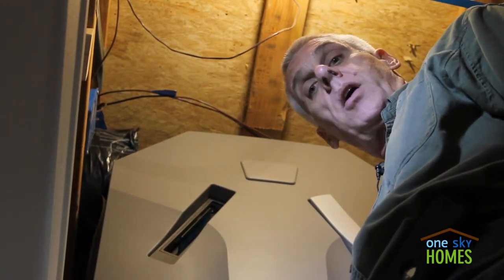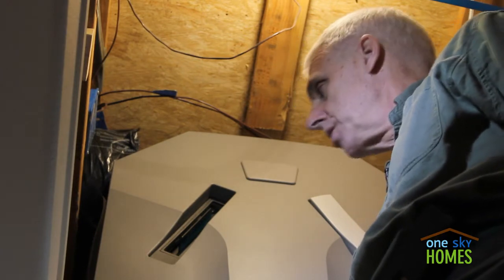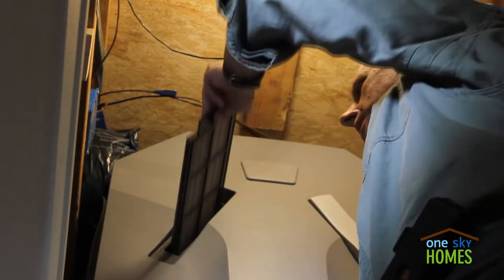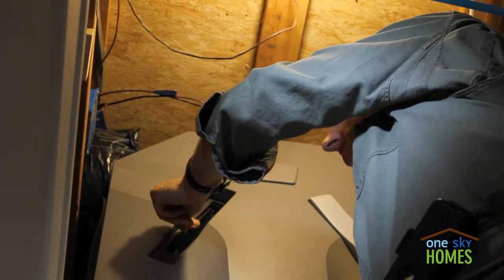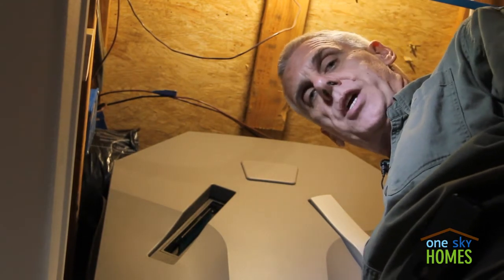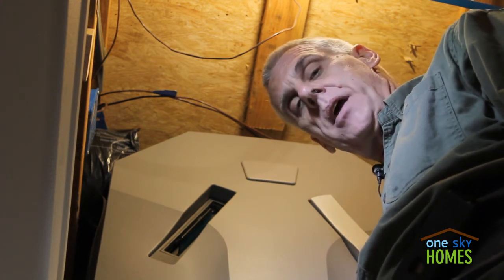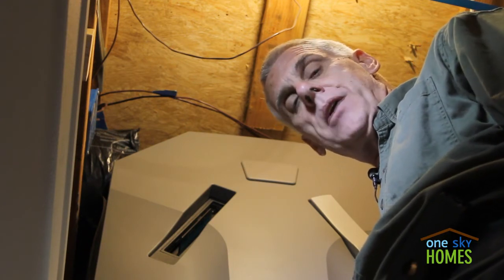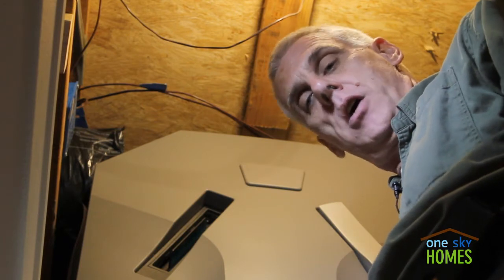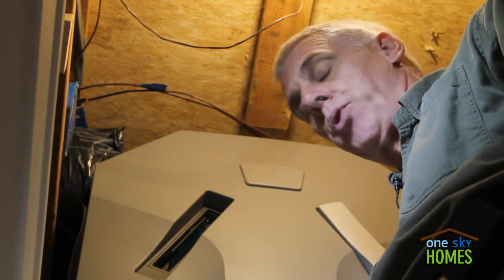In this project, we have the heat recovery ventilator mounted above the ceiling in the laundry room — a reasonably convenient space for occupants to change the filters. You can see here on this unit we have incoming and outgoing filters to ensure optimum air quality. Inside this unit is the heat exchange core. We have a constant incoming fresh air stream and a constant outgoing exhaust stream, never mixing, but passing through this high-performance heat exchange media. Only about 15% of the thermal energy inside the building is actually lost, ensuring a very high quality level of fresh, highly filtered air. Compared to the standard American home, this is absolutely superb indoor air quality.